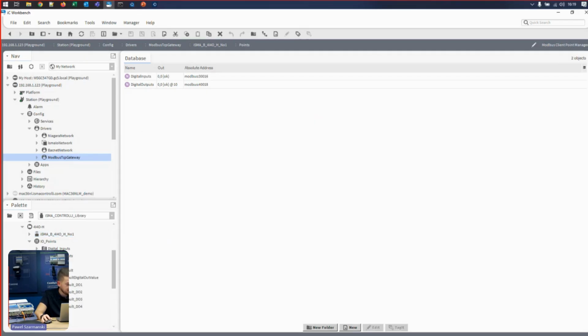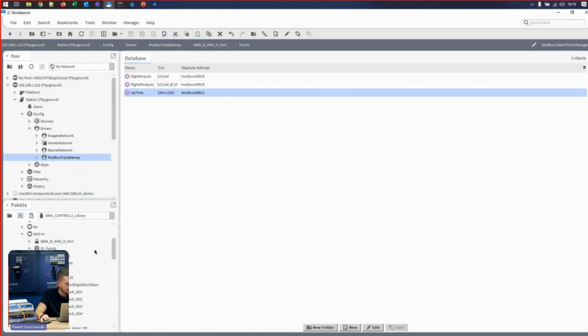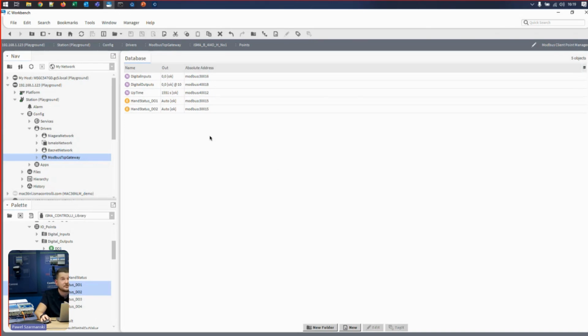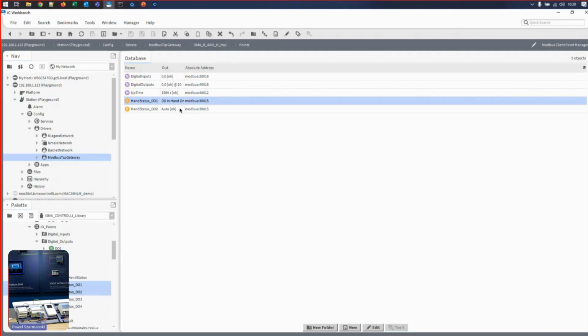Let's say we'd like to see the mode of this, let's say the uptime. We can just drop it here into the application and see all the values, for instance the hand status for the digital outputs. Let's drop 2 points — this is Modbus, and you can really easily drag and drop the points from Modbus. If we set the hand-auto switch on this mini module to the high state, we can see how it changes now in Niagara right now. So this is all working live as you see it.